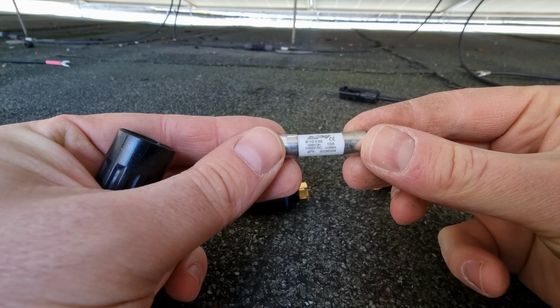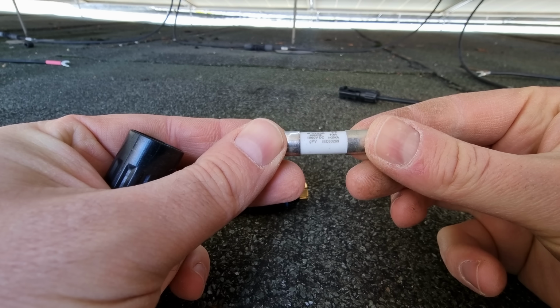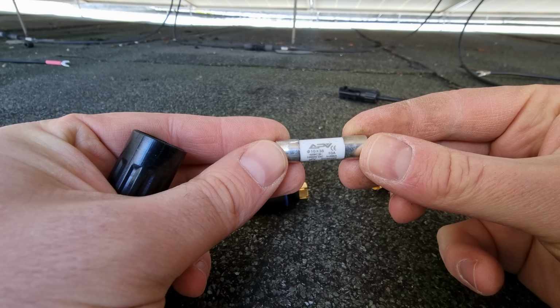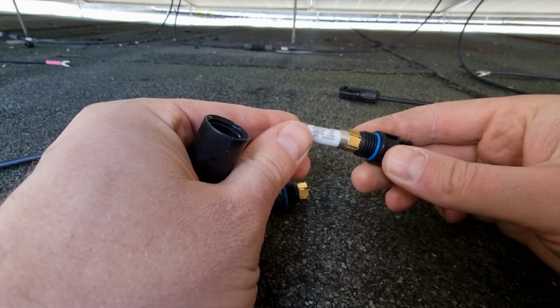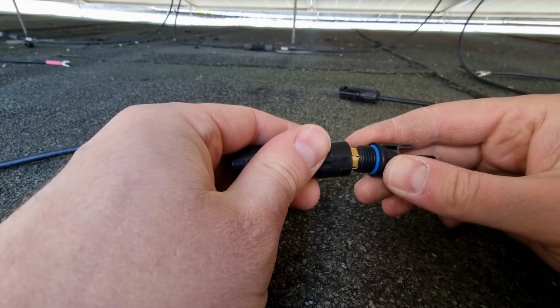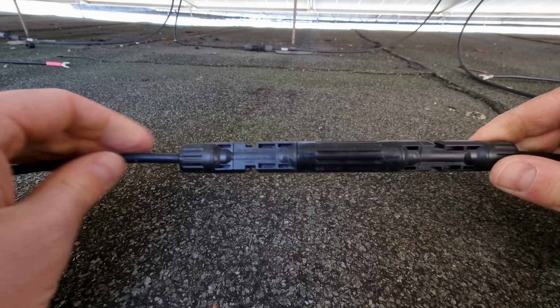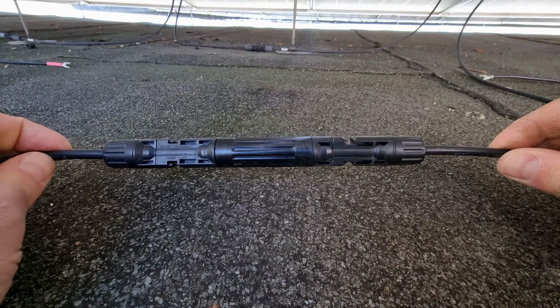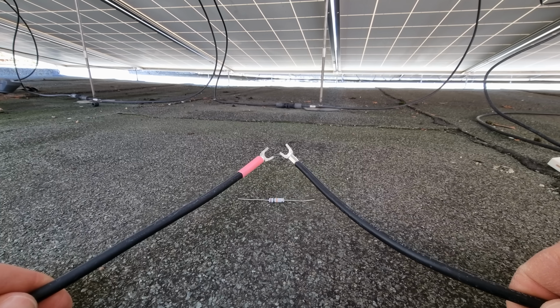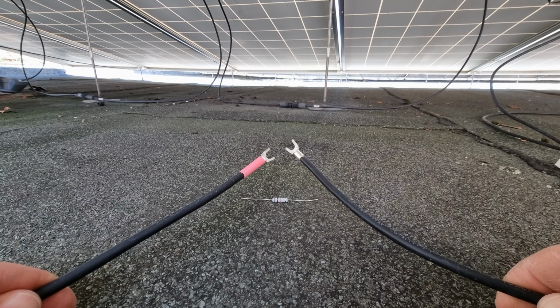Anyway, for ease of wiring, strings of similar voltage can be connected in parallel. It only takes a safe DC-rated per string fuse to reduce the risk of a fiery inferno on your roof that could otherwise be caused by a malfunction in one string presenting a load to the very dangerous kilowatt-capable high-voltage sources that are the other strings.